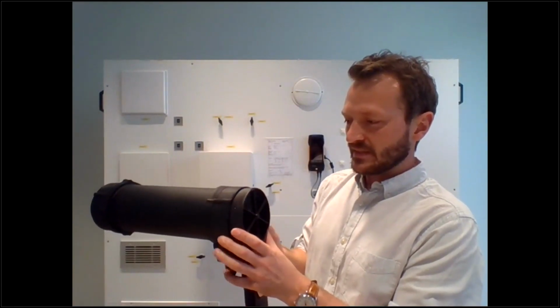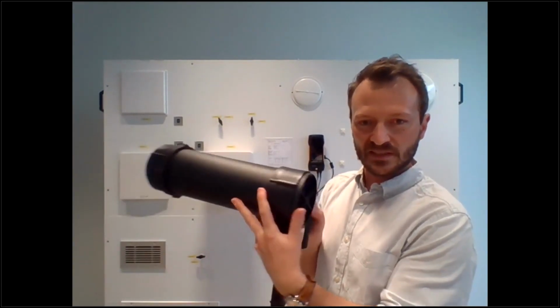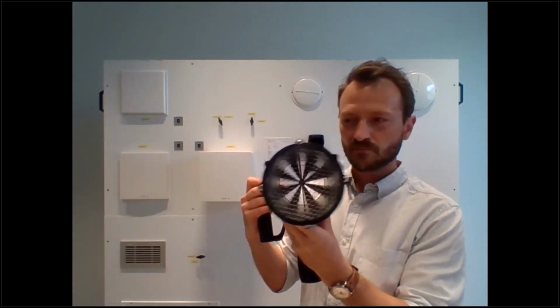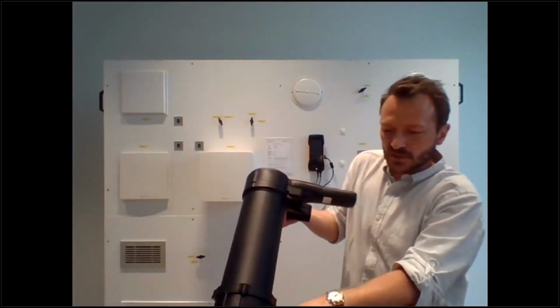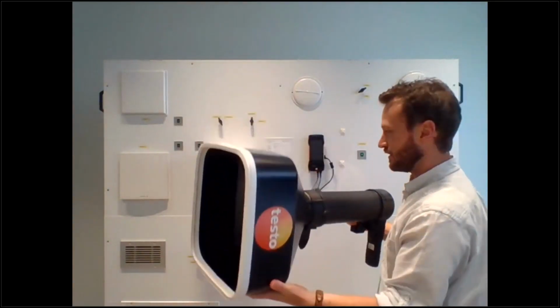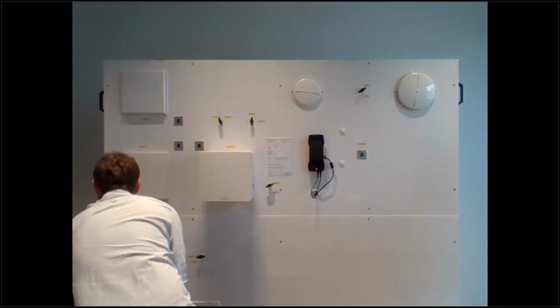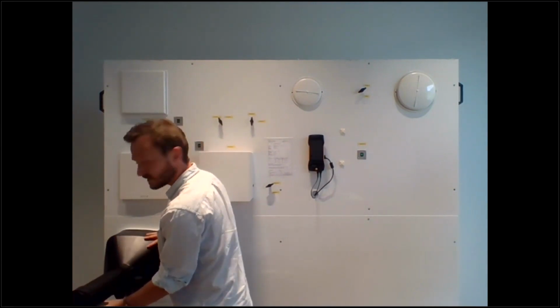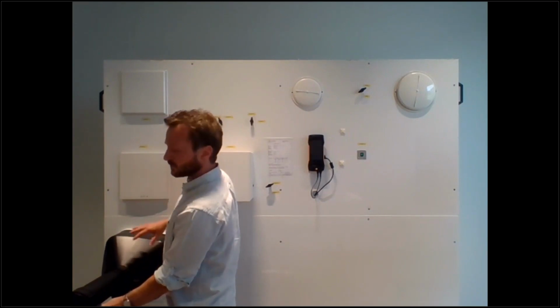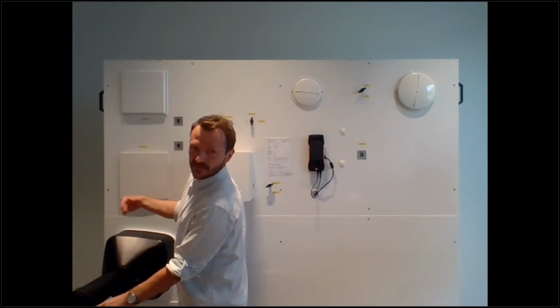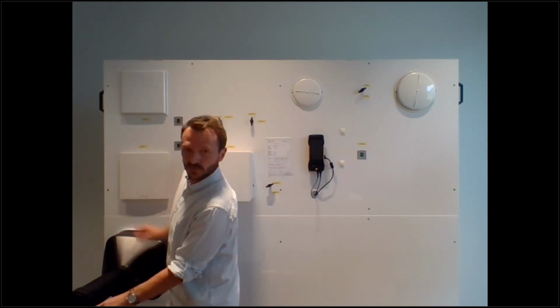As mentioned, this is exhaust air, and at the bottom we have supply air. We adjust the flow straightener, as you can see, and then add the funnel additionally. It's working, it looks like a bazooka, but it's pretty smart. We add it on the funnel, on the outlet, and then measure the volume flow. The air comes in with a little turbulence, then goes through the straightener and calms down, and the measurement is done pretty easy and fast.